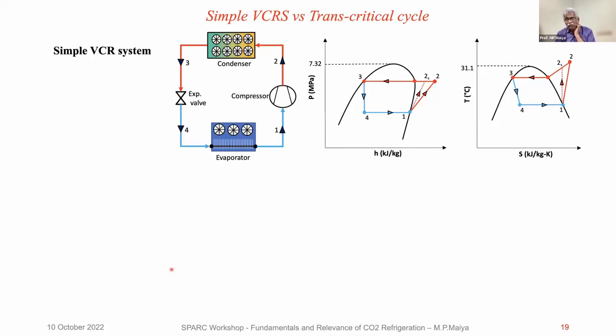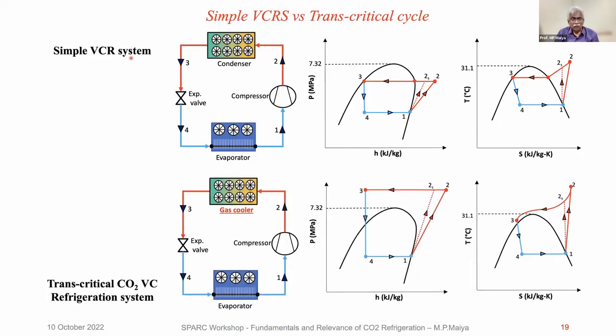So we are operating above critical, but also below critical. We have to see what the difference is. This is the conventional simple VCR cycle. Now, what is transcritical? Transcritical means there is no condensation. Here, in 2-3, there is desuperheating and condensing. Here there is no such thing. The whole thing is above critical. That means it doesn't condense, so the condenser becomes a gas cooler.